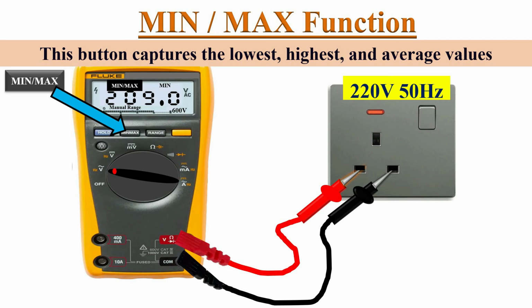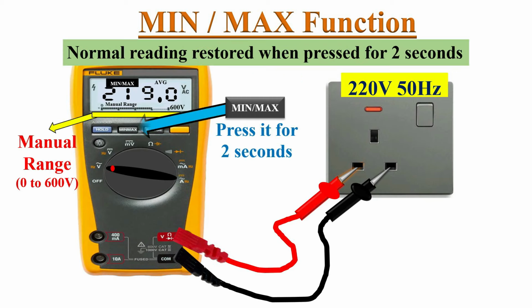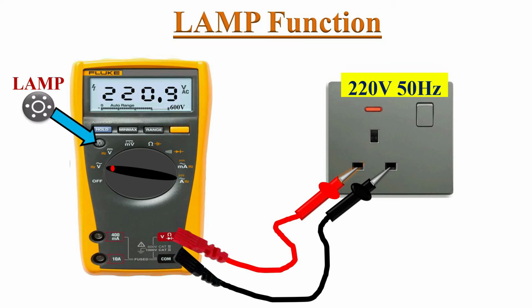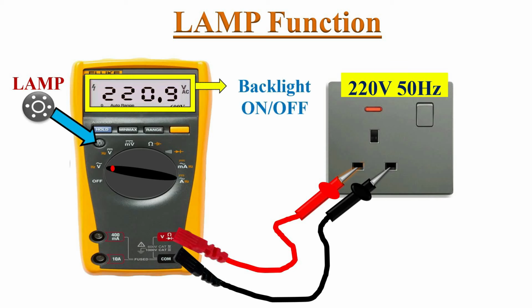Just press this min-max button again. The meter will enter into average value mode and displays the average measurement value of 219 volts AC. If we press this button continuously for up to 2 seconds, then the normal reading mode will be reactivated. This small round button is a lamp function of the screen. If we press this button, the backlight of the screen gets on. Press it again, the backlight gets off.